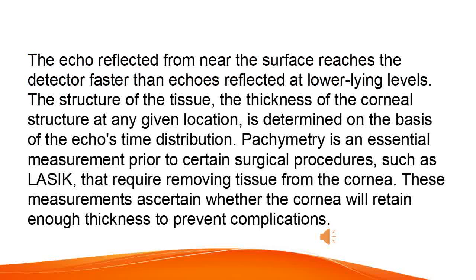The echo reflected from near the surface reaches the detector faster than echoes reflected at lower-lying levels. The structure of the tissue, the thickness of the corneal structure at any given location, is determined on the basis of the echo's time distribution. Pachymetry is an essential measurement prior to certain surgical procedures, such as LASIK, that require removing tissue from the cornea. These measurements ascertain whether the cornea will retain enough thickness to prevent complications.